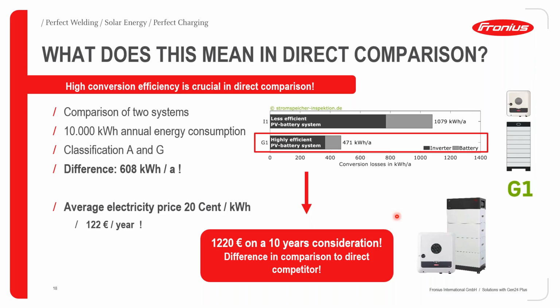What's very important for an installer to realize is that, if comparing two systems, you always need to take into consideration what would be the actual cost in the long run, or the cost savings in the long run. With the Fronius GEN24 Plus, our losses per annum were around 471 kilowatt hours, based on a 10,000 kilowatt hour annual energy consumption profile. Compared to the other system, which lost around 1,079 kilowatt hours per annum, this led to a direct saving of 608 kilowatt hours per annum, which is really an incredible value.